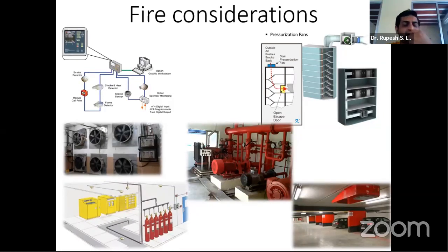Then coming to fire considerations, I think fire has today become a very important part of our building design itself. Gone are those days where we would only do things for compliance sake and compliance benefit. But now I think safety has become very essential, and it is also being mandated in a very strong way. I think people have also realized how important it is to have safety. So pressurization fans, of course, are a thing with the NBC. We need to have the staircase, lift shaft, lift well pressurizations, and we need to have the jet fans. We need to have the axial flow fans, and so on.